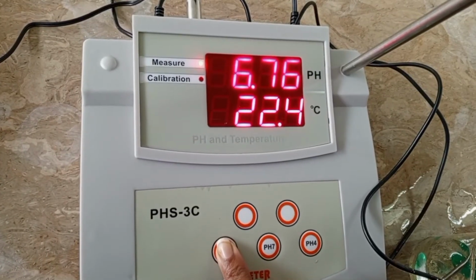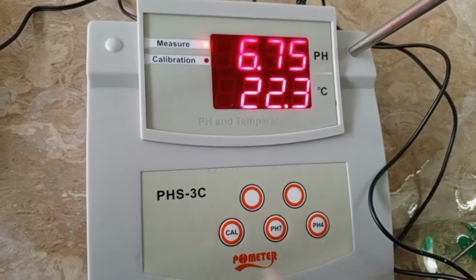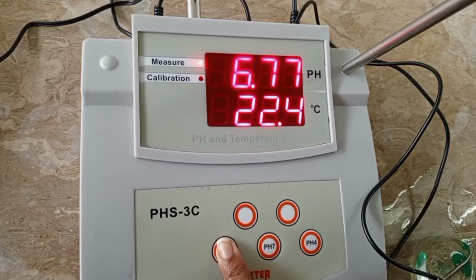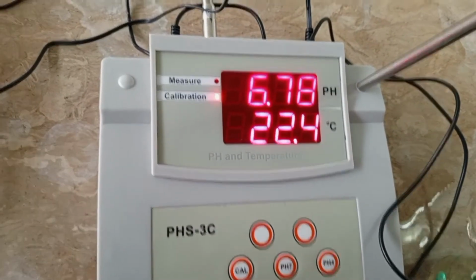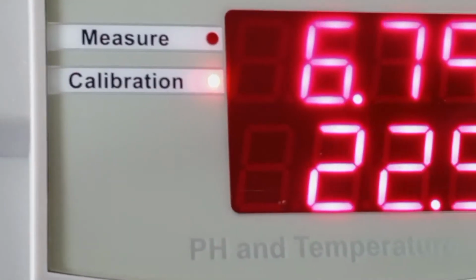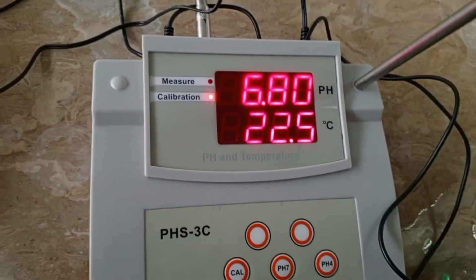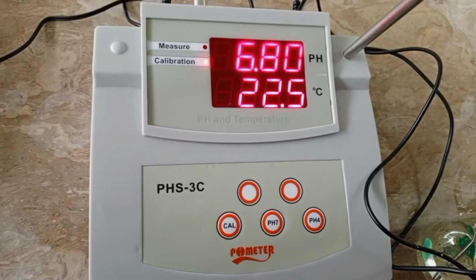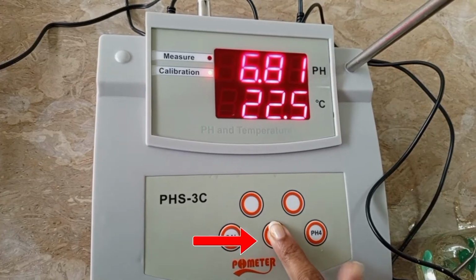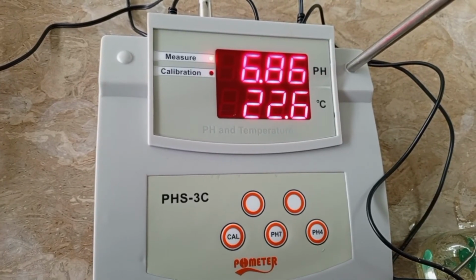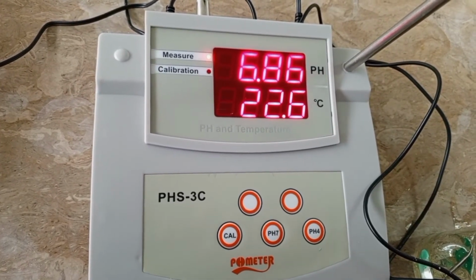In the same way you can also perform calibration with the pH 7 buffer. For that, keep pressing the cal button. The instrument will again show calibration and the red light is on. Now you can put the electrode within the calibrating solution of 6.86.